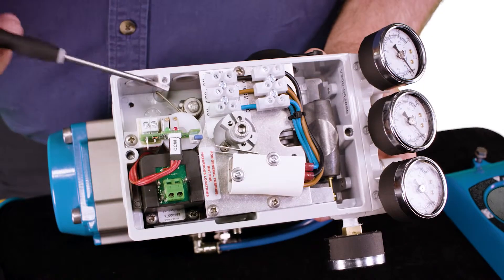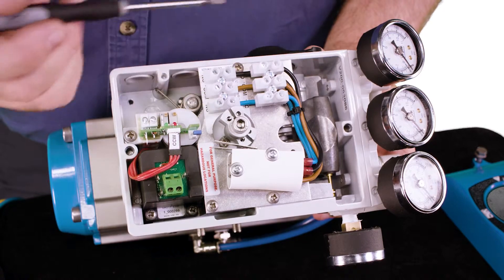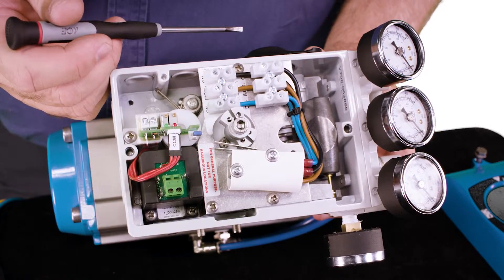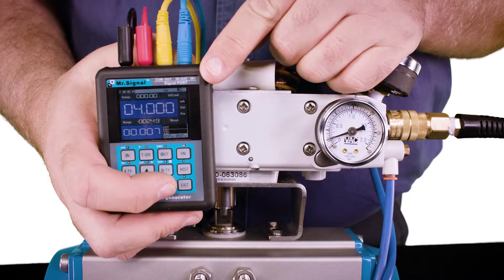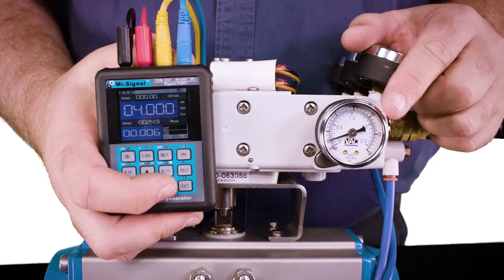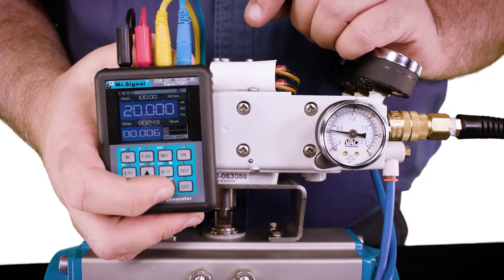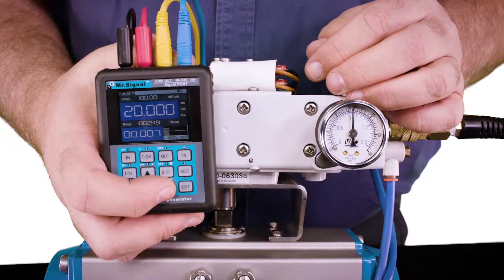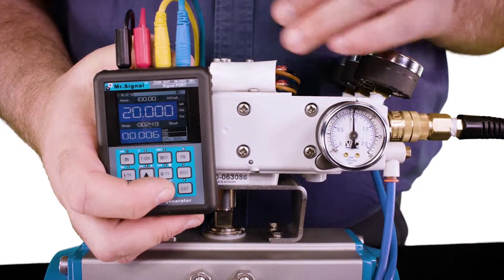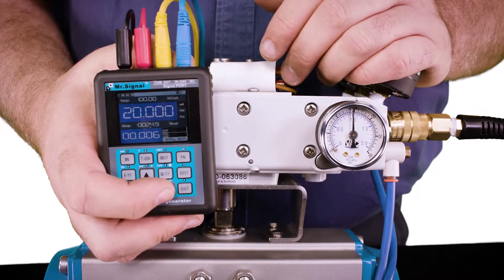Note that even with 4-20mA feedback and switches installed, the I/P module and the pilot valve are easily accessible and replaceable. To determine if the I/P is operating properly, we're going to put 4mA signal on the positioner, and this gauge should read approximately 3 PSI. When we put 20mA signal on the positioner, this gauge should read approximately 15 PSI. If we've got 3 PSI and 15 PSI at 4 and 20mA, we know that the I/P is operating properly.